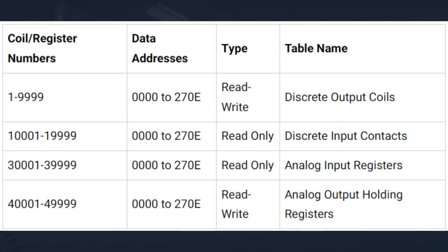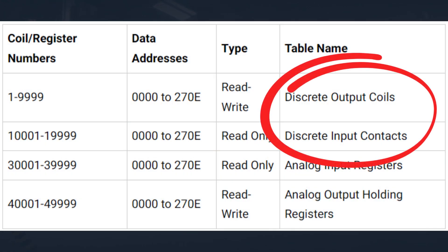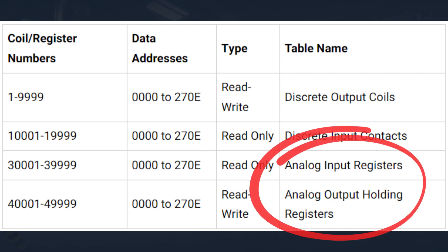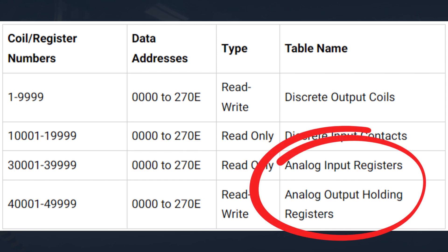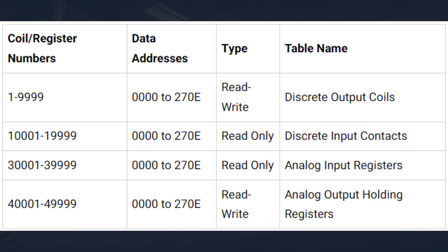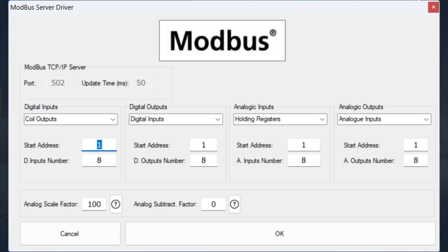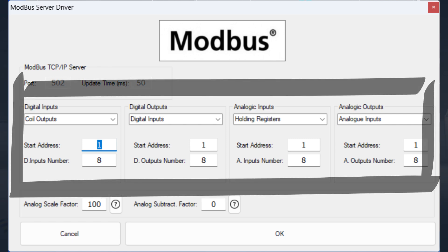Modbus memory is divided into four different areas. Discrete output coils and discrete input contacts deal with bit logic — they are either on or off, 1 or 0. Analog input registers and analog output holding registers are 16-bit words. The interpretation of this information in the word register depends on the Modbus client requesting the information. Every Modbus server on the network will have four available memory areas to read or write information. Please reference the manuals of your Modbus server to see how your device uses this memory. In the Machine Simulator, the Modbus server driver allows you to choose the memory location area for the digital inputs and outputs and analog inputs and outputs.